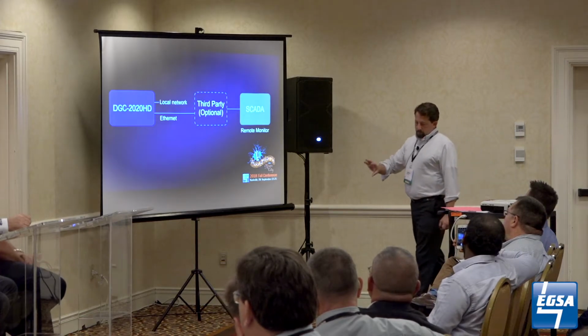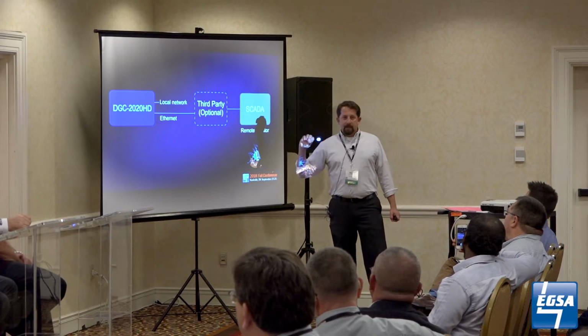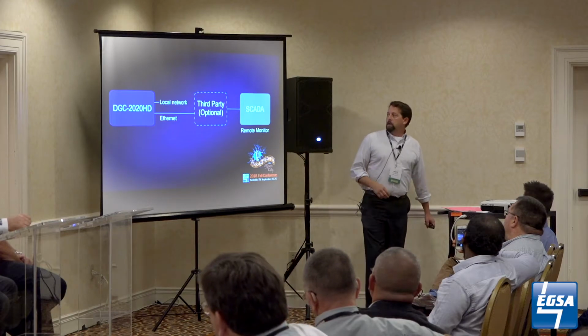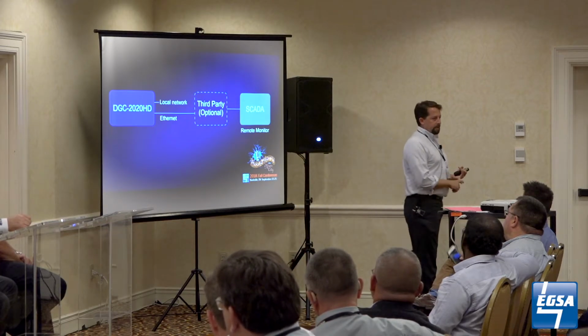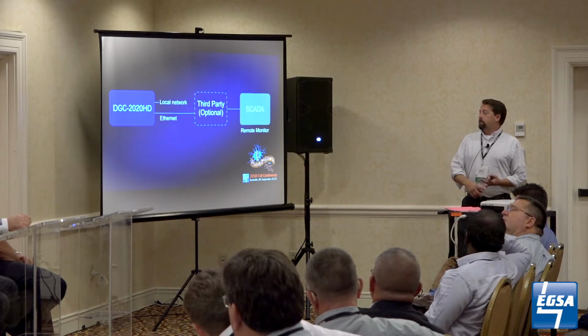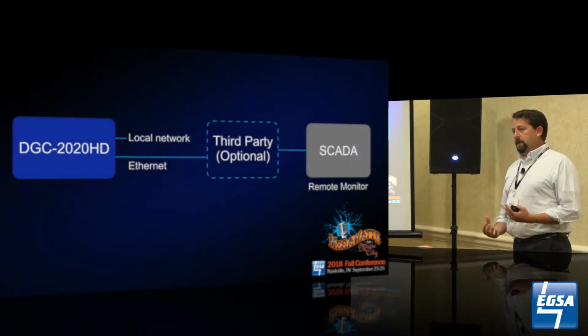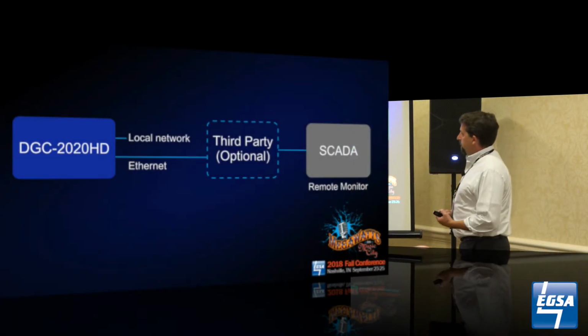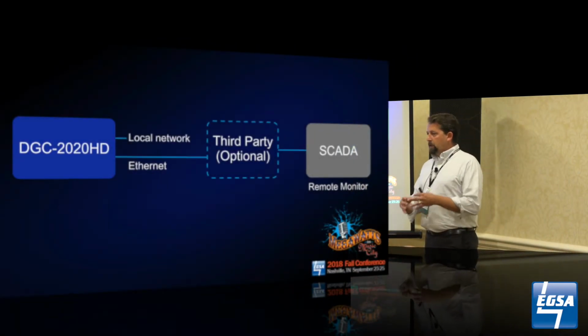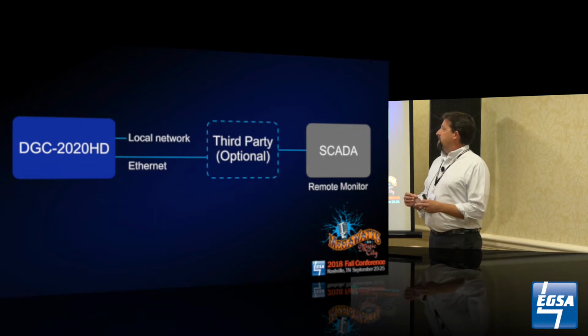So the controllers themselves are all tied by Ethernet at the remote level. They're doing generator and genset monitoring, distributed energy resource monitoring and control, breaker control and management, import-export control, and local loads. They're all tied in and communicate with each other.